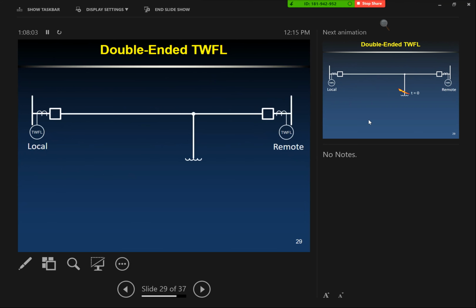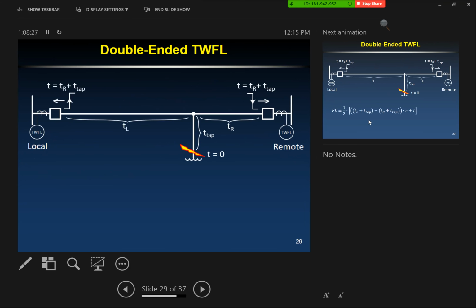And so what happens to the double-ended method when we have a tap down? So the fault happens at t equals 0, right? Now the waveforms arrive at, let's say, t tap. Now our time captured here is t sub r plus t tap. Ooh, this should be t sub l plus t tap. There we go. Just pretend that's an L. And so we plug that into our formula, so now it's T sub L plus T tap, T sub R plus T tap. These cancel out, right?